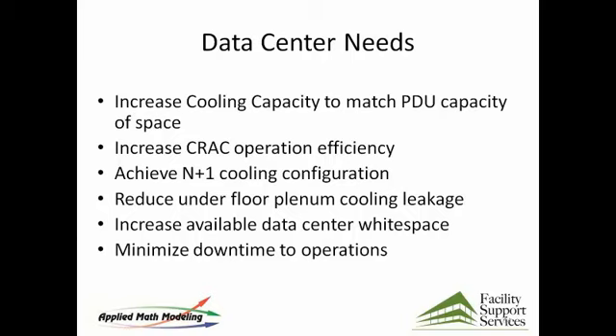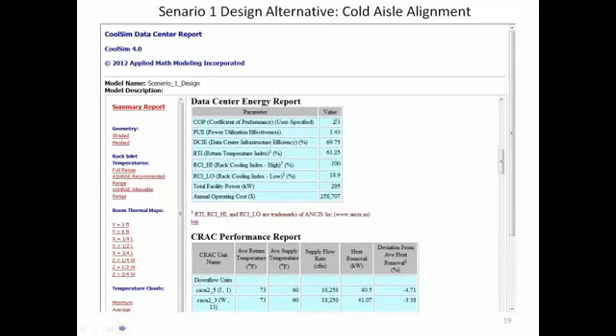So here we've run this model. Now, this is a cold aisle model, and let's first go to the summary report. There's no containment here. You're still what we call naturally convective on the return. Haven't changed anything here on the flow side or the temperature side. You did move to 60 degrees though on this one. You came up a little bit on temperature, which gave you a little bit better efficiencies. You moved up here to 2.3 on your COP.